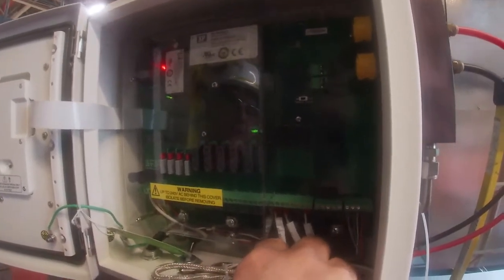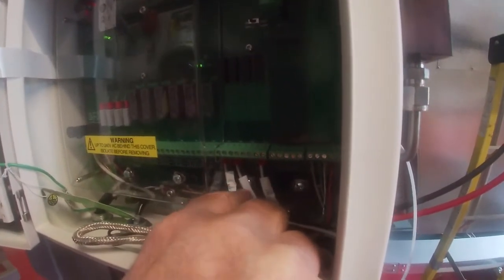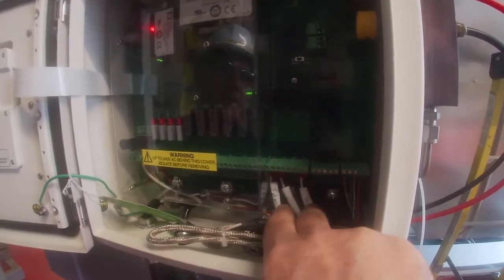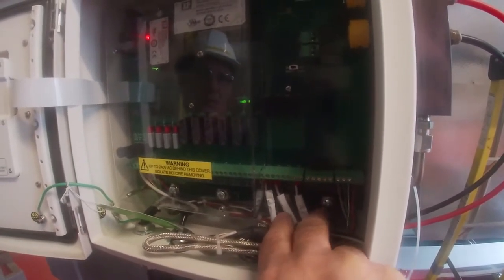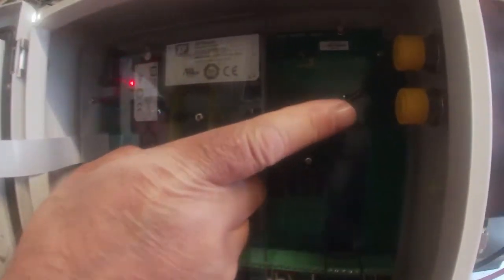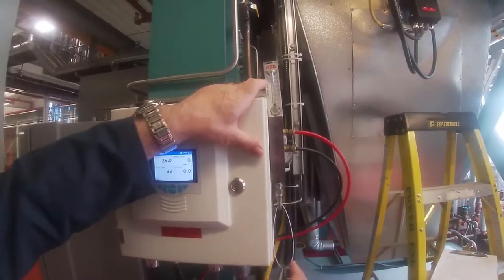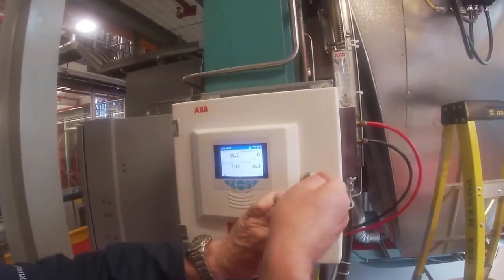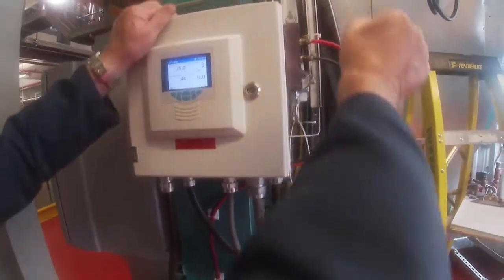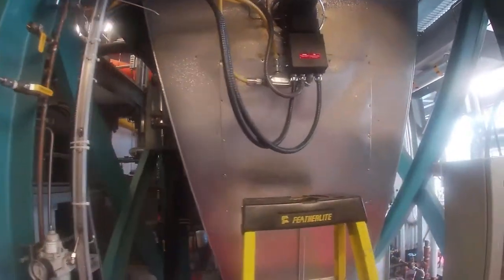This guy has got two 4 to 20 milliamp signals coming out, one for oxygen, one for combustibles, and then it's got another one that's coming out showing us combustion efficiency. To calibrate the analyzer, there's some solenoids that are activated, and if I look back into that corner over there, those two yellow things are the solenoid valves that are going to admit the zero gas and the span gas. And then if I close this door back up, there's an electronics cable that goes from here up to the sensor array, which is up top.